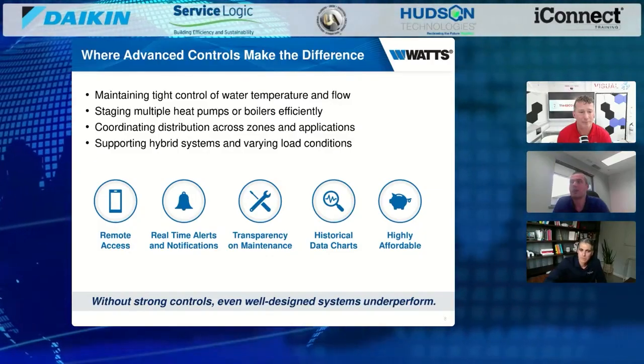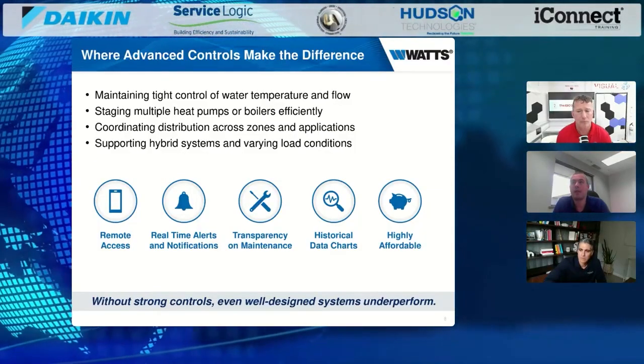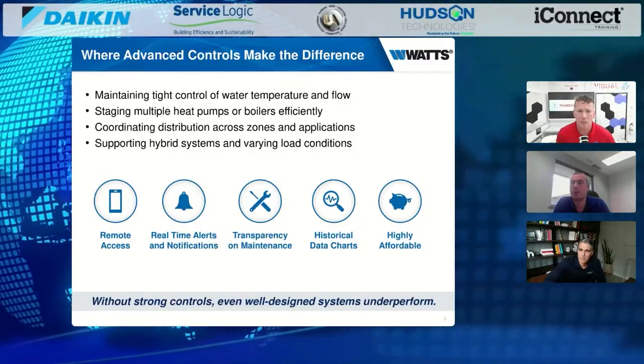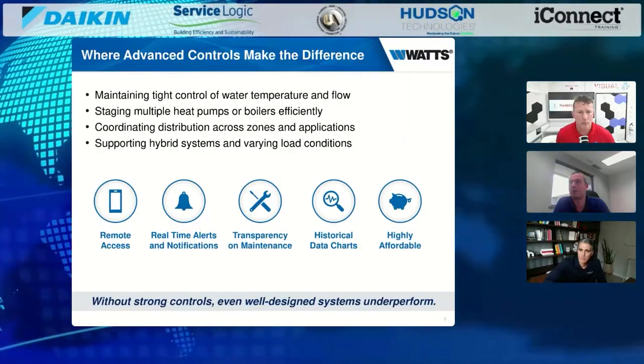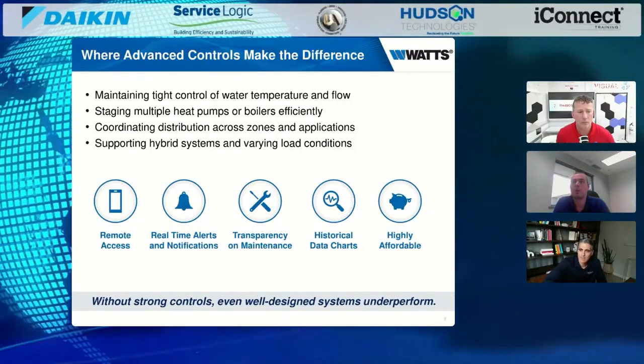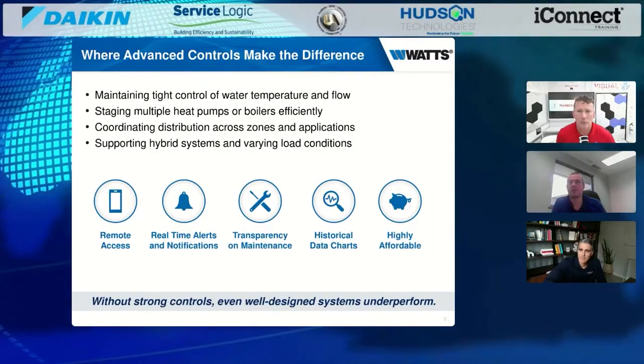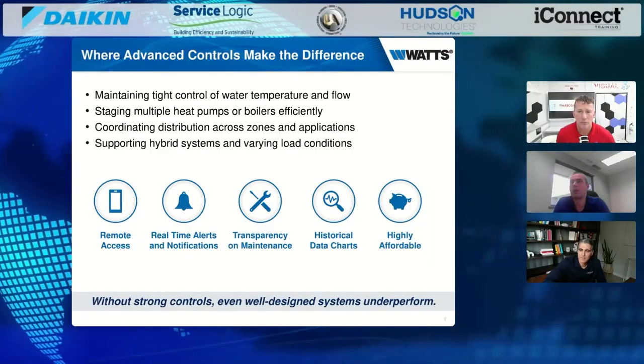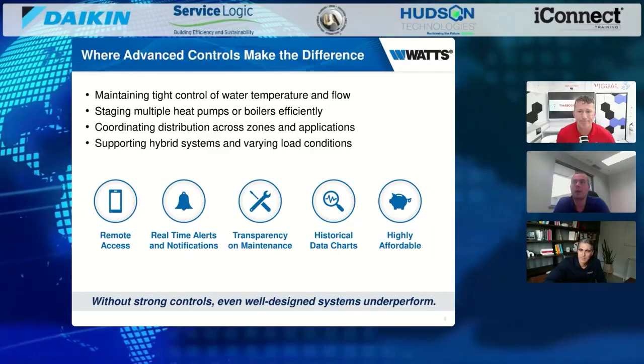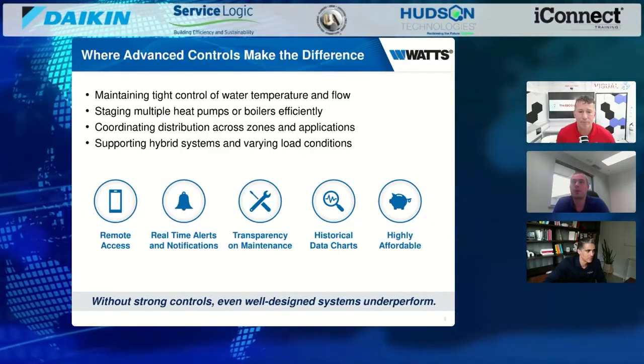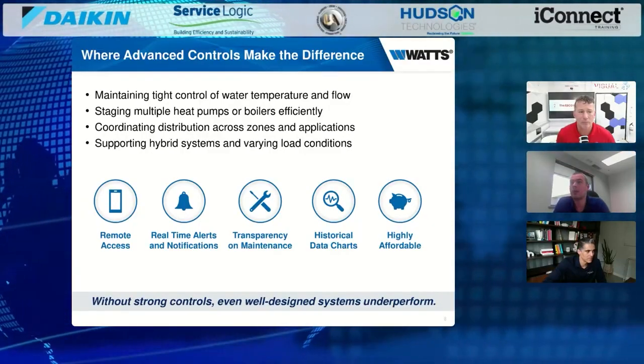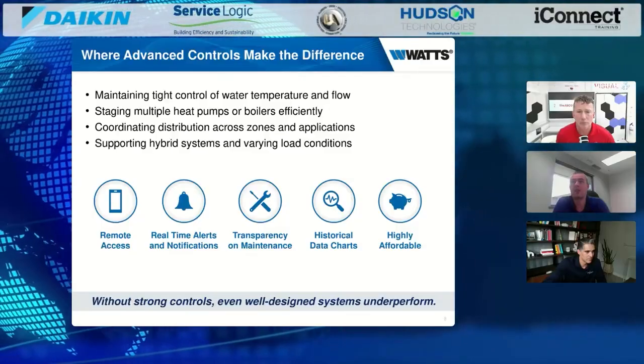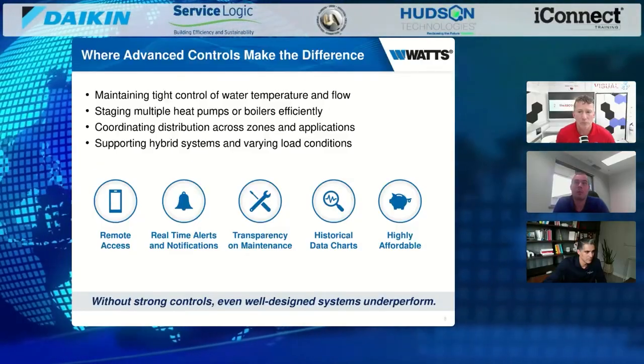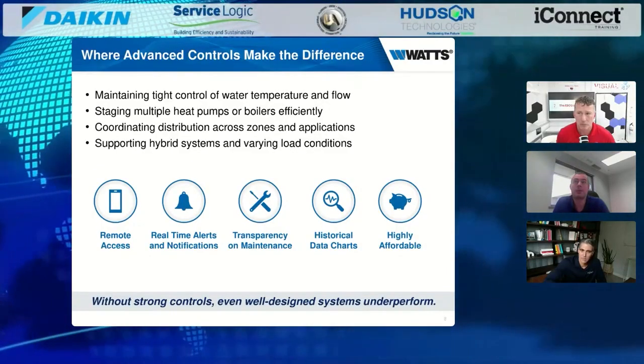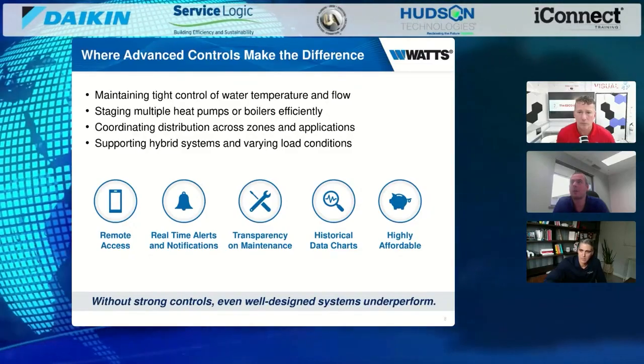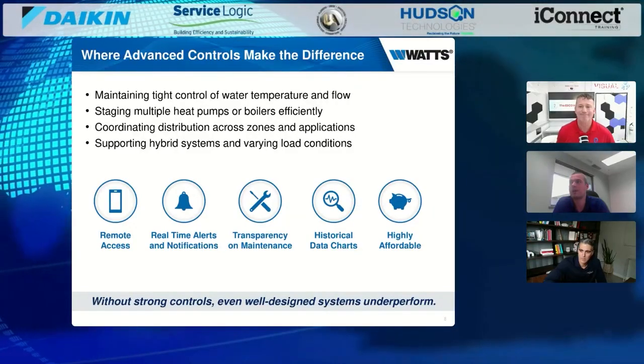The goal of a system for heating is to run the water at the lowest temperature possible, and for cooling to run it at the highest temperature possible. That's only doable with this analytics and visibility on the system. You can adapt with an outdoor reset curve, but now with indoor temperature sensors throughout the building, you can have indoor feedback, so you can react to what the building's actually doing at that specific minute. That's going to be a lot better control and a lot better comfort for the tenants.